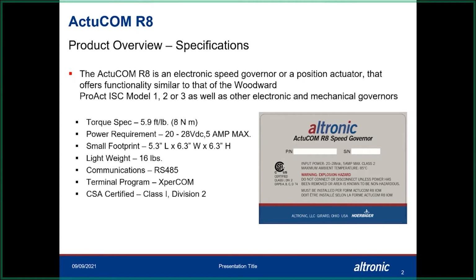Speaking of competitors, we have a small footprint that almost lines right up to the other one. It is about 8 pounds lighter than our competitors. We have the RS-485 communications terminal program, class 1 div 2 also. This product here was really developed to combat our competition. Our connections to it will line up with the Woodward product, so making a retrofit on it is pretty desirable to the customer.